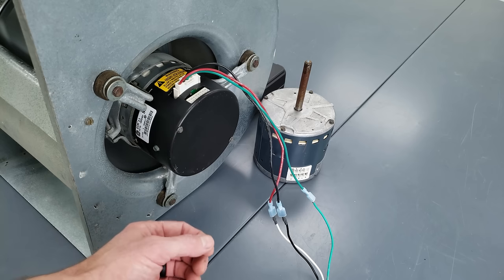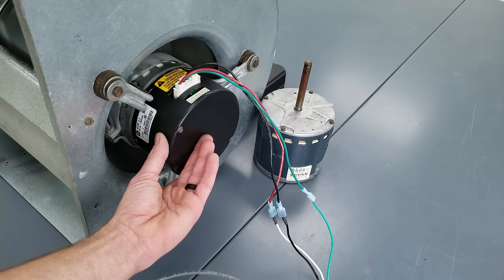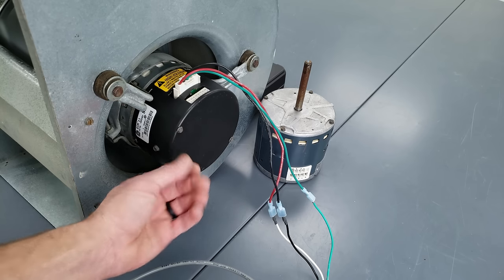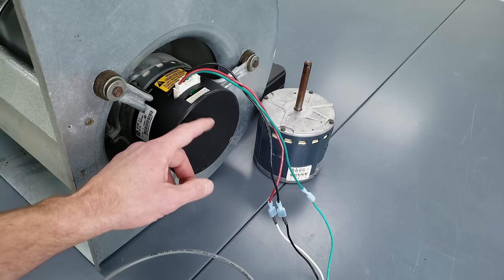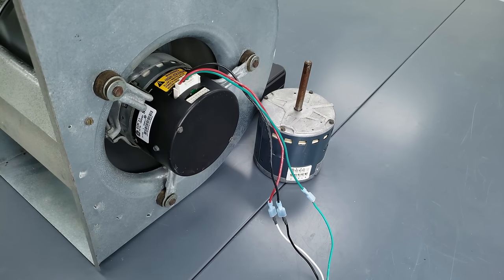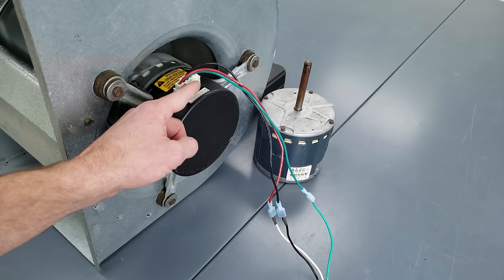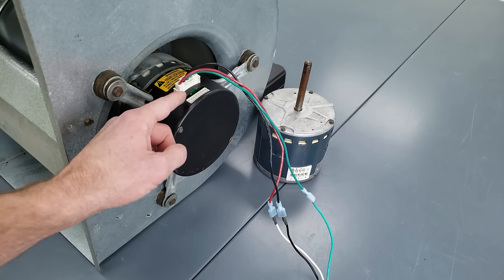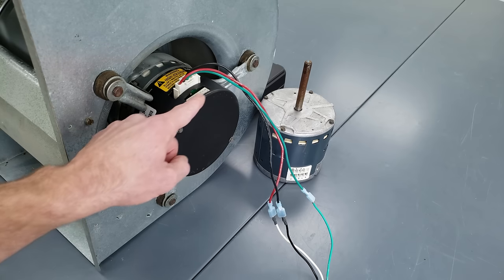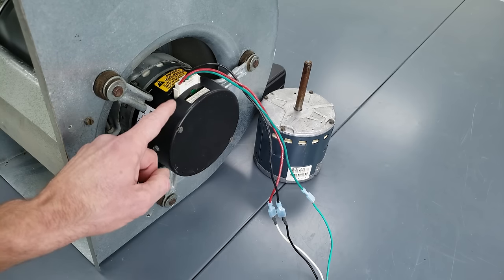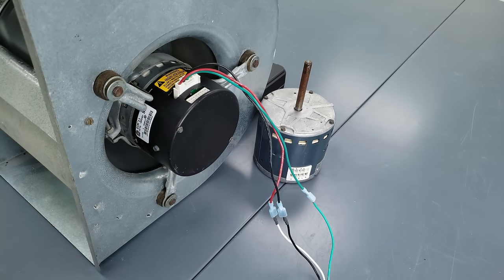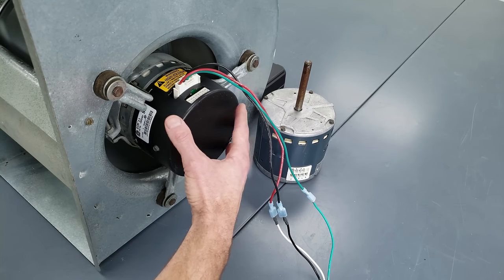So an ECM blower motor may fail in a manner where it receives a signal to turn on but never ends up shutting off. You've got to remember that you're always going to have your main power hot up over here, but this is your signal communication for when the blower motor turns on and turns off. In this case, this motor module is going to have to get replaced.